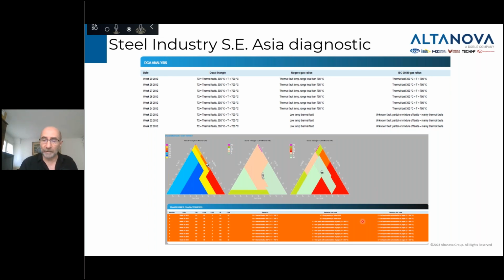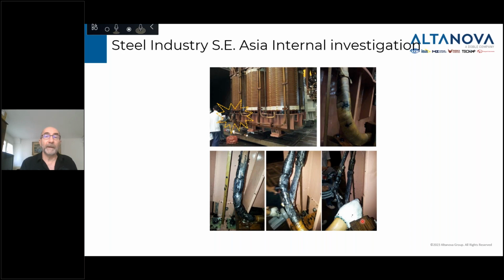So here, that specific customer, taking that into consideration, shut down the transformer, took it offline, and opened it up. And this is what they found on this specific connection here. You can see the insulation was mostly completely burned out, right to the cable. So again, by using the right, very accurate DGA measurement and using very accurate diagnostic tools, they were able to predict that some kind of fault was going on in that transformer, and make the right decision to shut it down and do some repair before that fault became even more critical in the operation of their transformers.